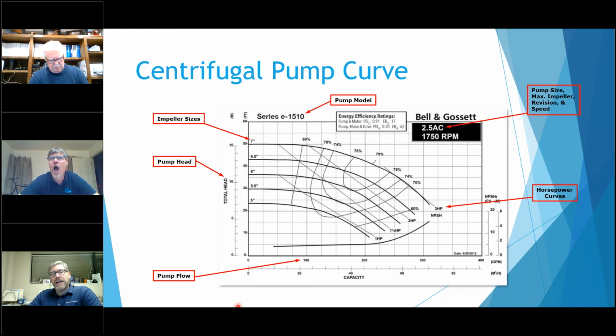These light lines coming across here are your horsepower curves. Anywhere you choose a pump, you need to make sure that you have at least that horsepower. So here, if we're looking at 200 GPM and going up to 25 feet of head, we're right here. We can't use a 1.5 because the pump actually uses more than 1.5 horsepower. So we need to use a 2 horsepower motor on that pump.